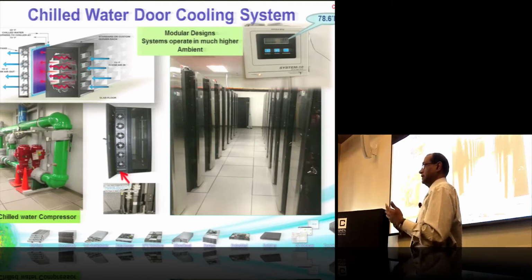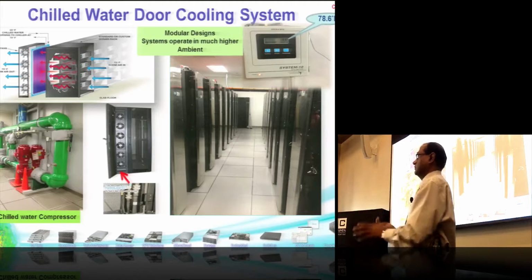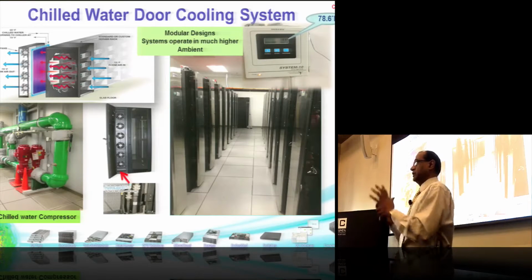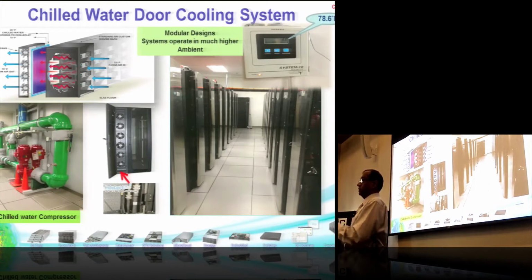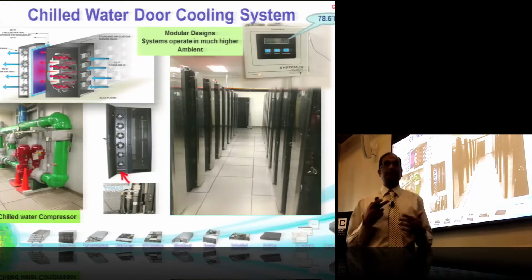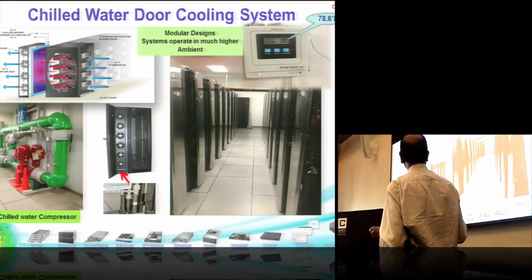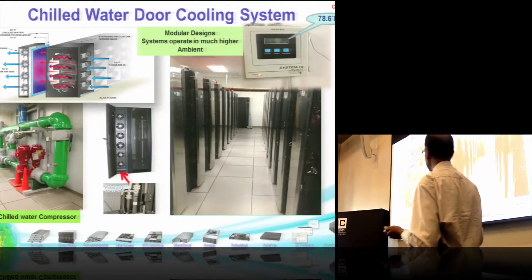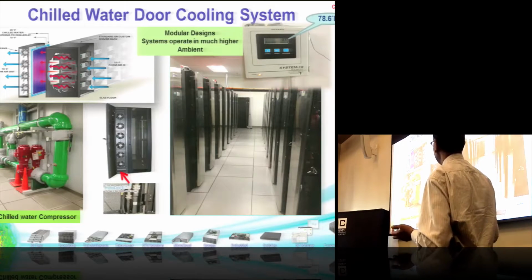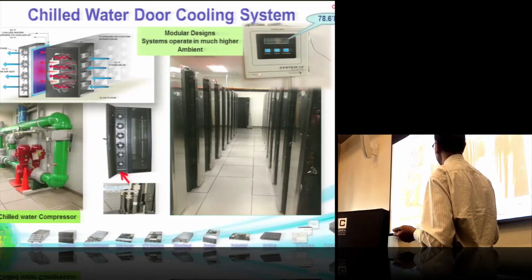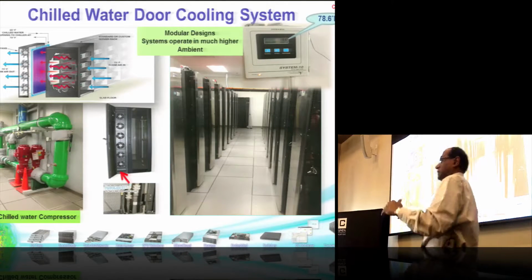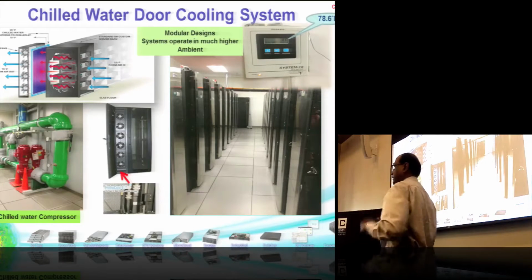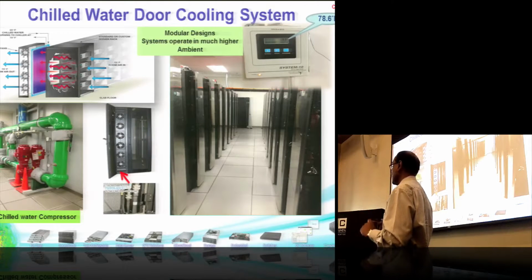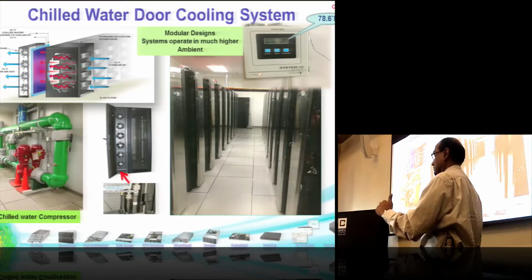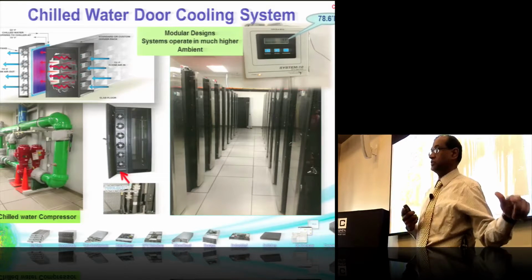This one actually still uses the existing chilled water infrastructure, except what you do is you replace either the rear door or the panels, or it can be modular, depending upon your server power densities. The most efficient would be to replace your back panel with a chilled water door, so basically you have modules or a door that captures the hot air, maintaining circulation of hot air through the fans and cooling system.